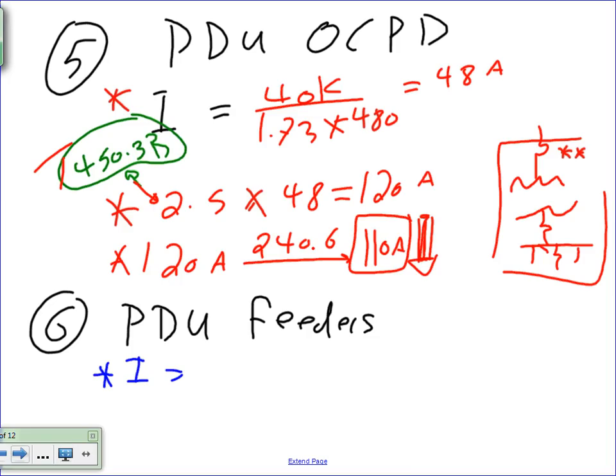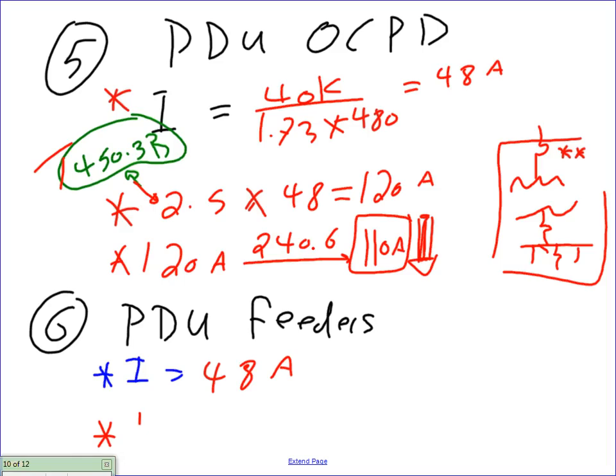Okay, let's go to number 6, guys. It's the PDU feeder. The same thing. You take the 48 amps, the feeder to the PDU, and then we need to multiply it by 1.25 for continuous load. I thought we did that one. 48, right? Did they say 480? You're saying it wrong, but right. What do you call this? Dyslexic, or no? That's not dyslexic. It's called Chad. Chadixic, there you go. Or Chadizing, or whatever we call it. Anyway, 1.25 times 48. What is it? 60? 60 amps. Thank you.